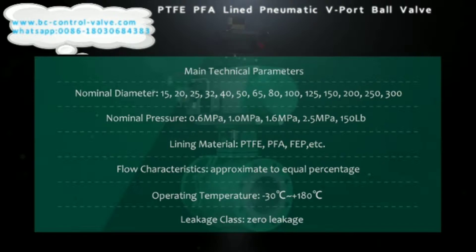The main technical parameters of the pneumatic lined V-port ball valve are: nominal diameter from DN15 to DN300; nominal pressure of 0.6 MPa, 1.0 MPa, 1.6 MPa, 2.5 MPa, and 150 LB. Available lining materials include PTFE and FEP. Flow characteristics are approximate to equal percentage. Operating temperature range is from -30°C to 180°C.